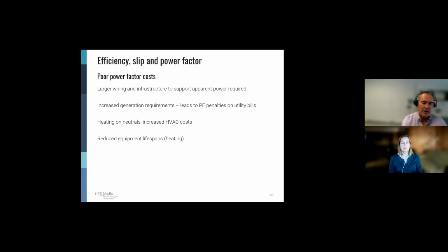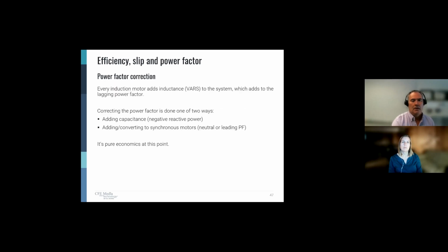Additionally, you can get heating on the neutral conductors, which increases your air conditioning costs. And again, anytime we heat up electrical equipment, it reduces its lifespan. It just doesn't like that. So we talked about every induction motor adding inductance to the system, which adds to the lagging power factor. So we need to correct that as opposed to just paying for it.